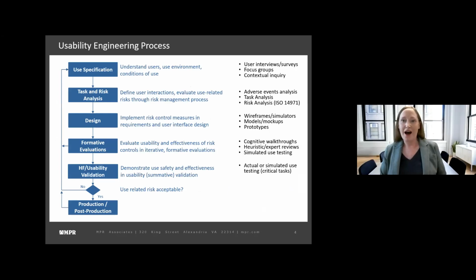The basics from a high-level view start early in user research and planning by defining the use specification for the device, understanding the users, the use environment, and conditions of use for a device. That leads into task and risk analysis, where we define user interactions and start to evaluate hazard-related use scenarios and use-related risks through application of the risk management process. A key part of that is to start to identify risk control measures that can be used to mitigate use-related risks that can help feed into the requirements and drive the user interface design of the product.